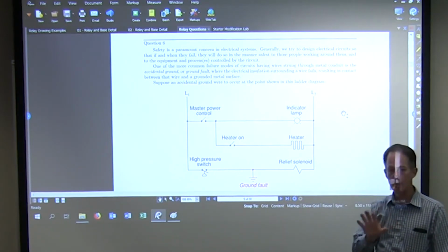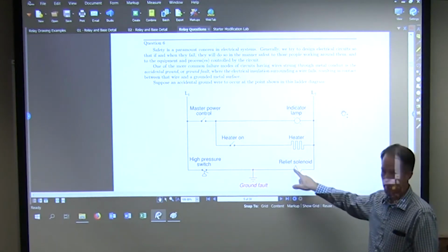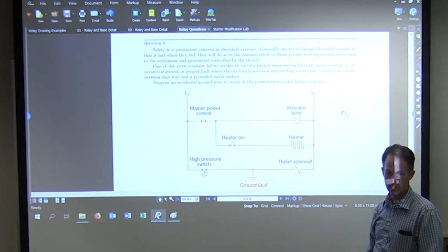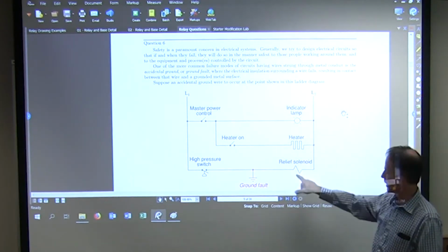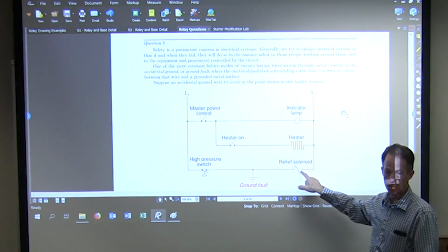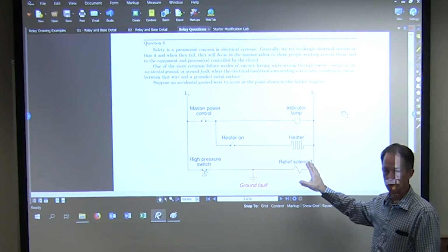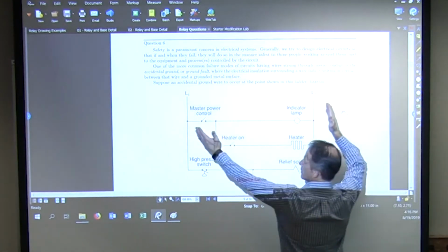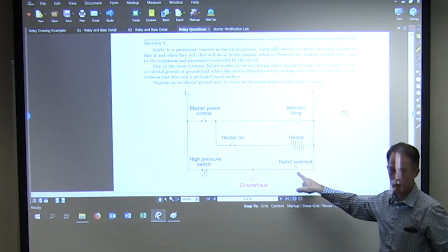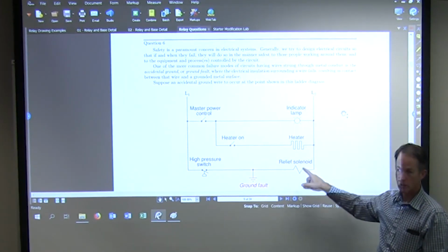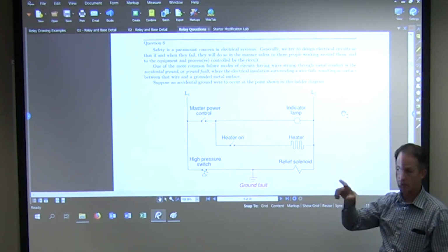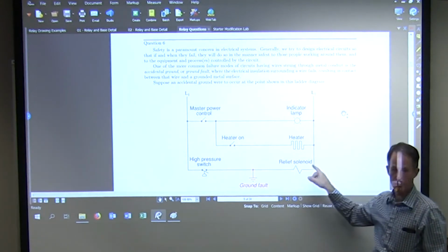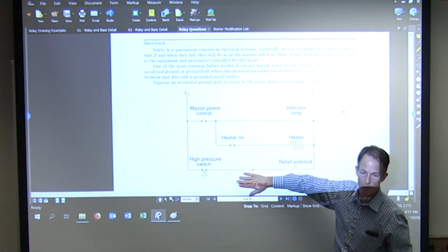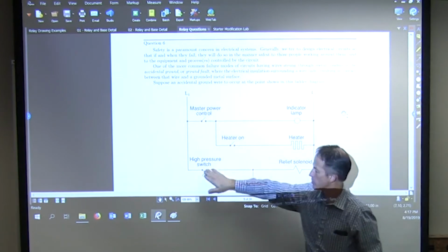So let me give you some numbers. Say this has 240 ohms of resistance. On a 240 volt circuit, I get 1 amp through there normally. Does everybody agree with that? On 240 volts, I have 240 ohms of resistance, so to do the math you'd end up with 1 amp current flowing through here if the ground fault wasn't there. So this switch is still open.